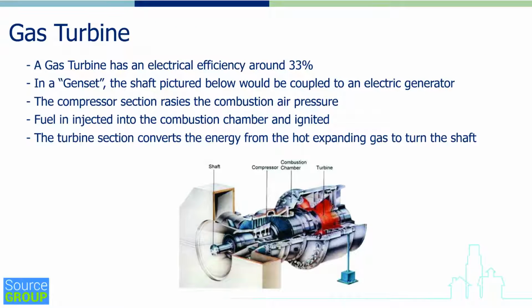Gas turbine. A gas turbine has an electrical efficiency, as we previously stated, around 33%. In the picture below, normally the electric generator would be coupled to the gas turbine at the shaft, and that's referred to as a genset. The compressor section raises the combustion air pressure from atmospheric pressure up to a compression ratio of about 10 to 1, so that would be 147 pounds per square inch.